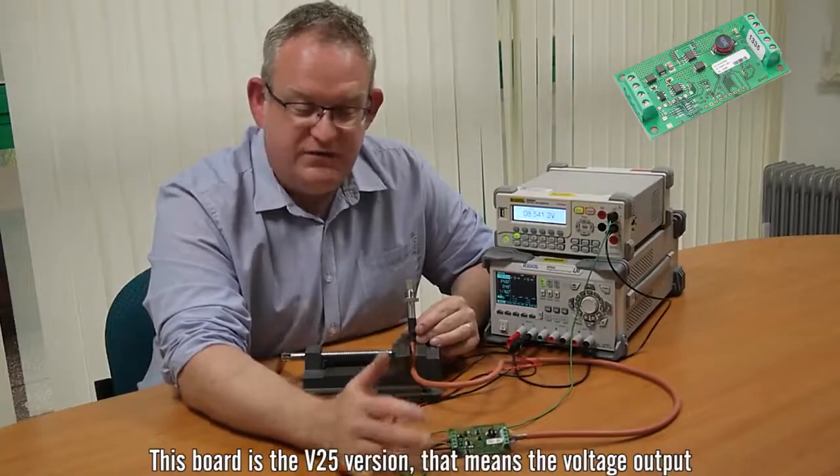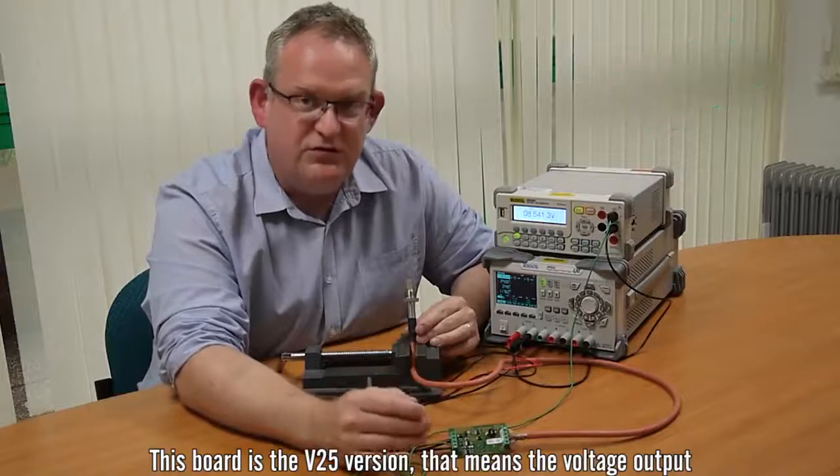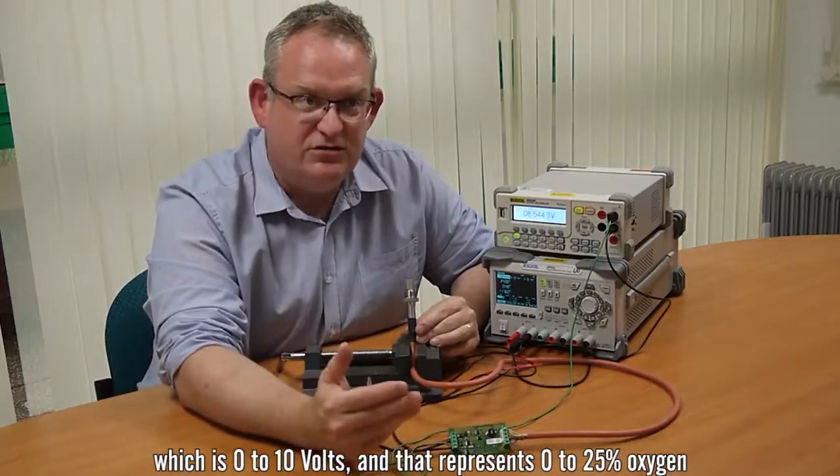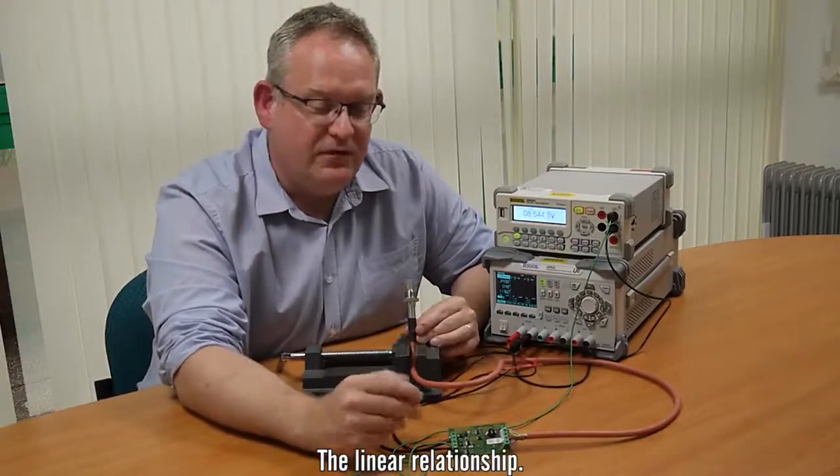This board is a V25 version that means a voltage output which is 0 to 10 volts and that represents 0 to 25 percent oxygen, the linear relationship.